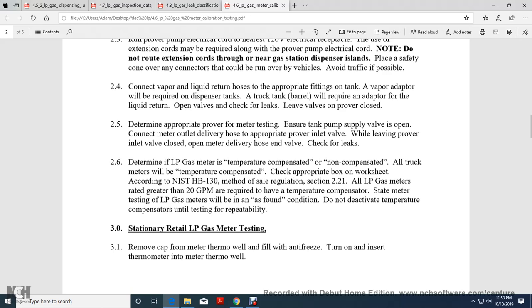Open the meter delivery hose end valve and check for leaks. Determine whether the liquid petroleum gas meter is temperature compensated or non-compensated. All truck meters will be temperature compensated.